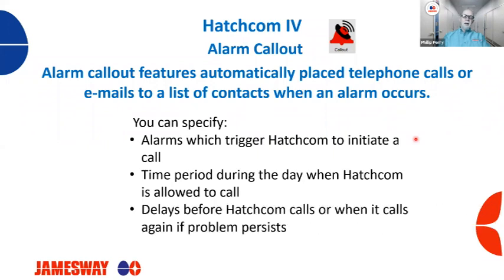Another thing, you can set the delay before Hatchcom calls out. So say your machine is bumping a high temp or whatever, you could put a minute or 2 minute delay in there just to buffer that machine and allow it time to recover, so that you don't have a lot of what we would call nuisance alarms, where it would be calling you or emailing you.